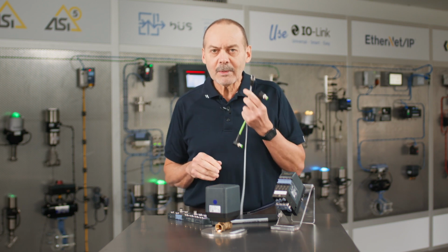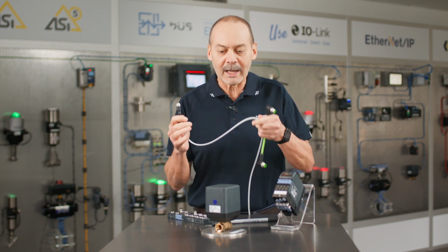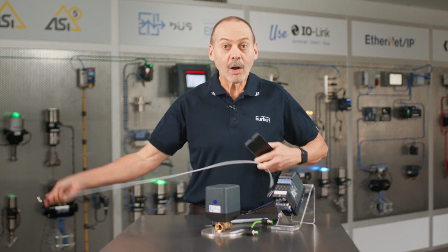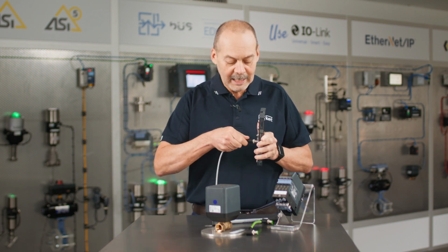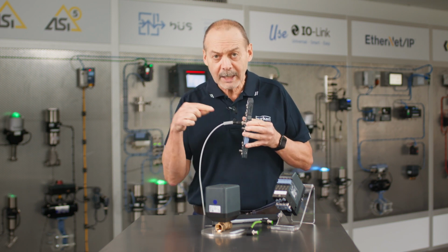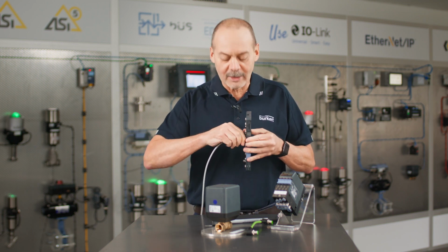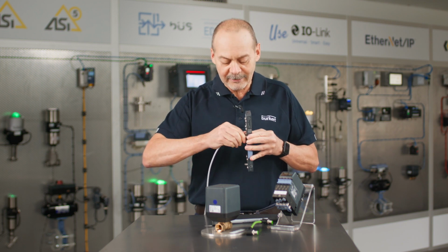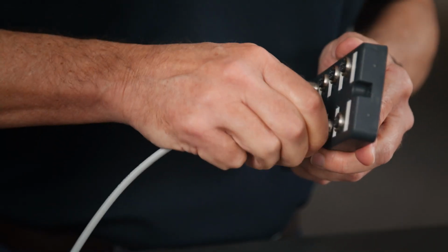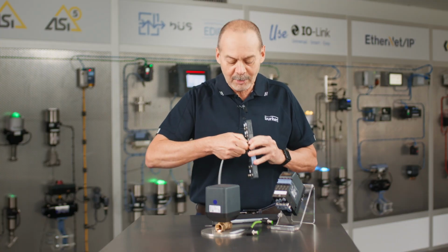Okay, next one is the most important take home I want today, is that you connect the cables with the right amount of force. Generally what we find is people take a cable, they take a block and they connect it by hand. Now, quick word on this. Always be patient and take your time. Don't cross thread one of these, because if you cross thread a block, you might find that you're not going to be able to recover from that. So wriggle it in, make sure you can push it safe. You should be able to wind it most of the way with your hands. If you have to use a spanner in that early stage, one would suggest you've got a problem already.